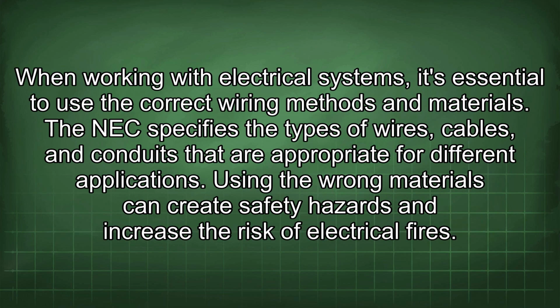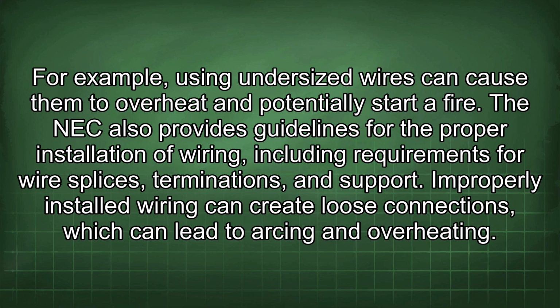When working with electrical systems, it's essential to use the correct wiring methods and materials. The NEC specifies the types of wires, cables, and conduits that are appropriate for different applications. Using the wrong materials can create safety hazards and increase the risk of electrical fires. For example, using undersized wires can cause them to overheat and potentially start a fire. The NEC also provides guidelines for the proper installation of wiring, including requirements for wire splices, terminations, and support. Improperly installed wiring can create loose connections, which can lead to arcing and overheating.